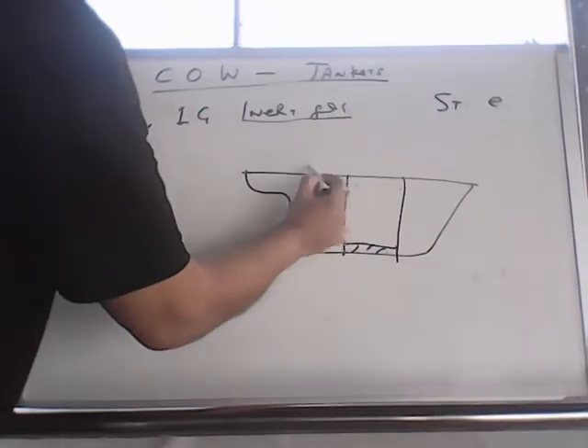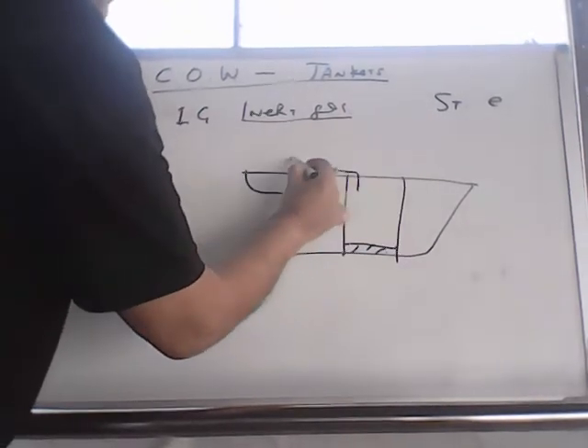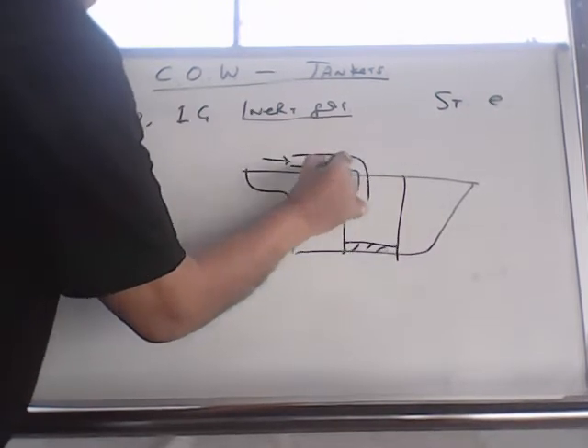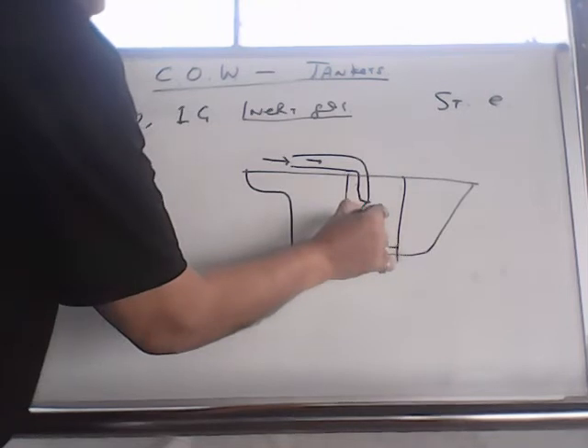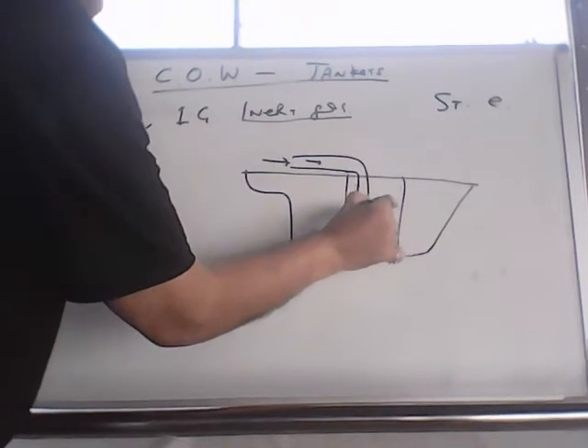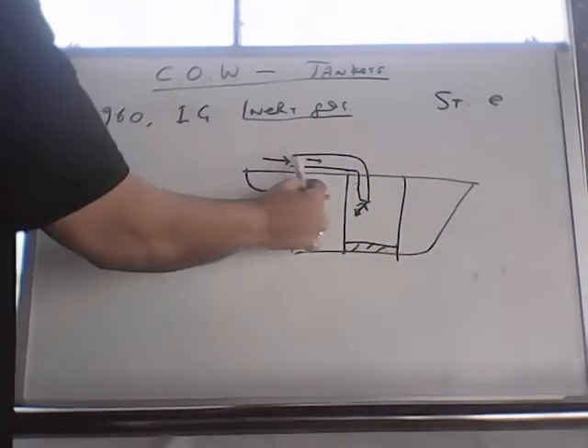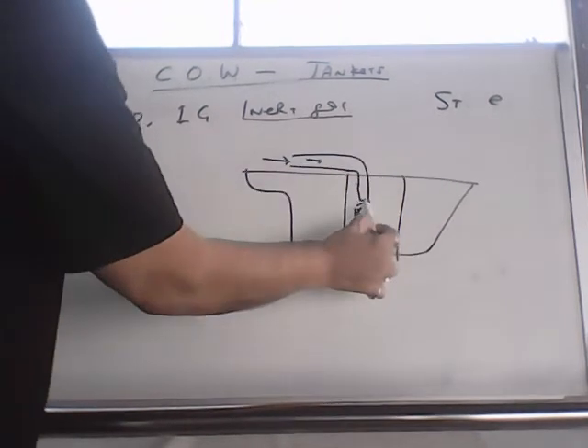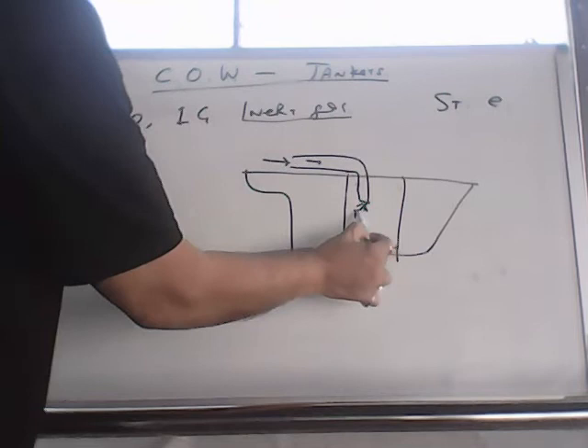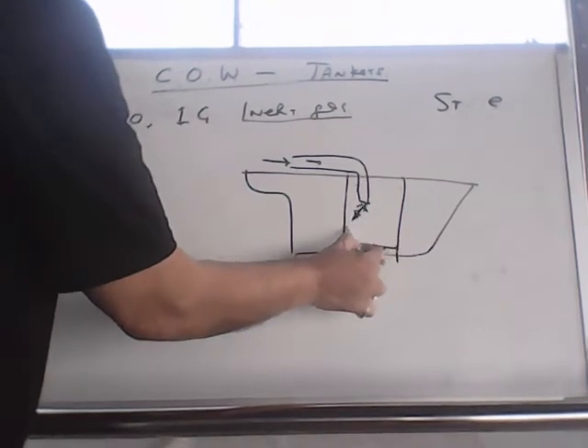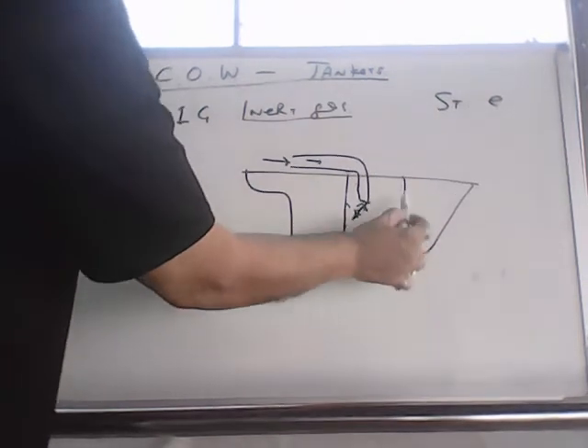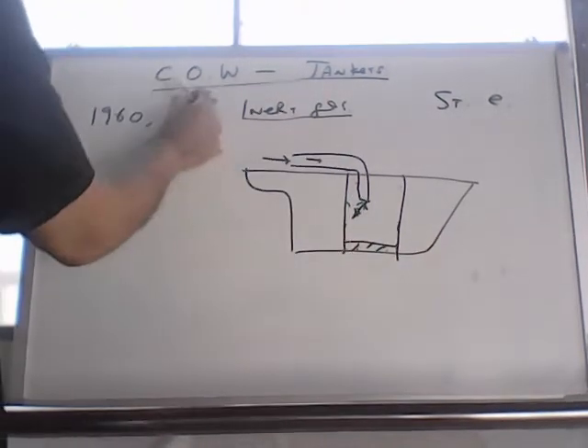Then on the tank cleaning pipeline the same cargo from another tank is pumped inside the tank cleaning line and you have tank cleaning machines. So this same cargo from another tank is pumped in the tank cleaning line and through the tank cleaning machine this hits every part of the cargo tank and the cargo tank gets cleaned by crude oil washing.